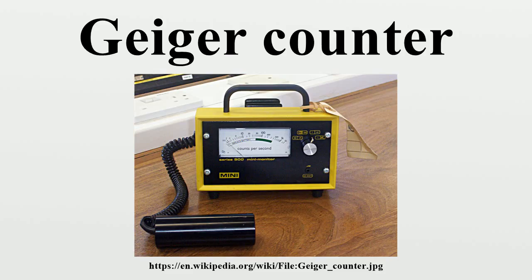positions. But the two-piece design allows easier manipulation of the detector, and is commonly used for alpha and beta surface contamination monitoring where careful manipulation of the probe is required or the weight of the electronics module would make operation unwieldy.